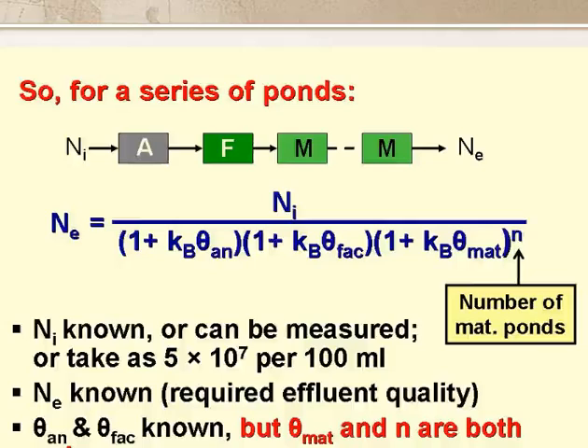For a series of ponds, remembering that the effluent of one pond is the influent to the next, we can derive the equation for NE shown on the slide. This says that NE — the number of E. coli per 100 ml of the final effluent — equals NI, the number per 100 ml of the raw wastewater, divided by a term for the anaerobic pond, one for the facultative pond, and one for the maturation ponds raised to the power N, where N is the number of maturation ponds.